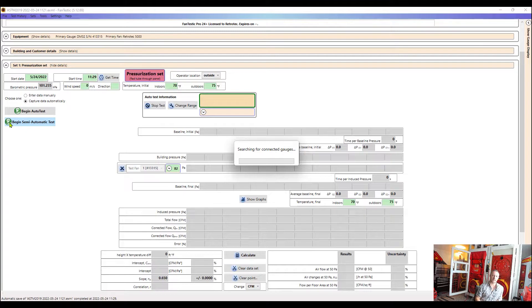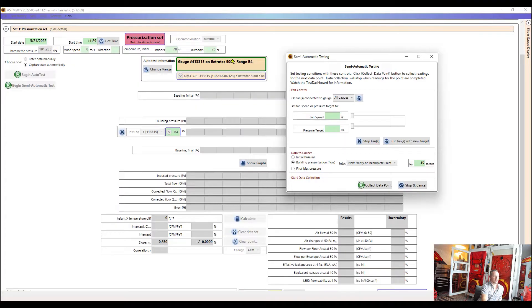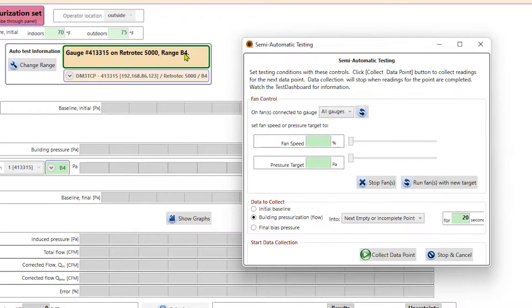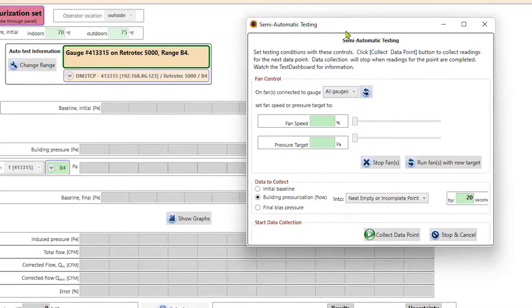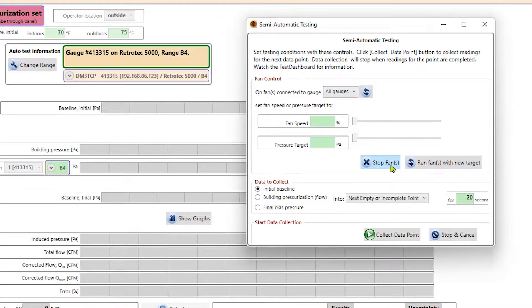It's going to search for that gauge again to find our equipment. So we can go ahead and start collecting data. So we can see it found my gauge. And it has the correct fan that the gauge is operating with the range that I had it set to. And it also opens this window here. And I can choose to collect a baseline or some building pressures with the fans running. First, I'm going to do the baseline.